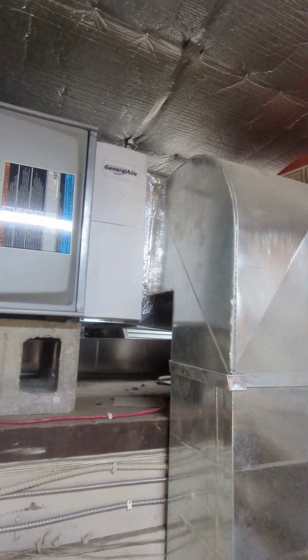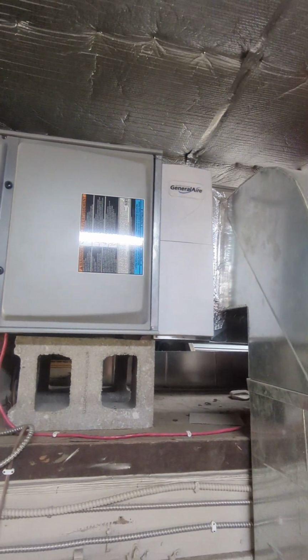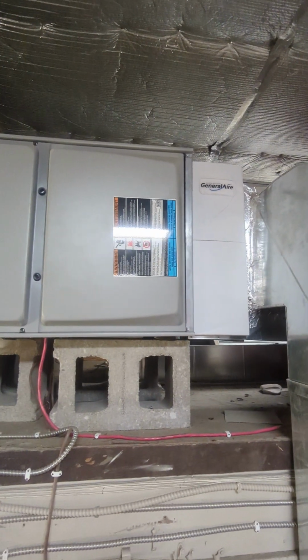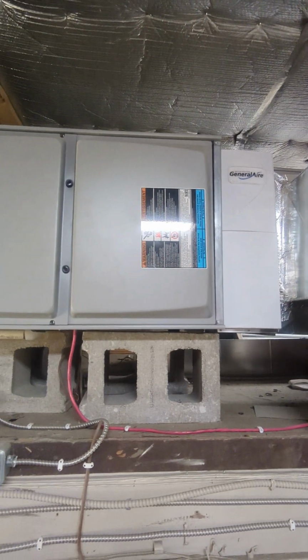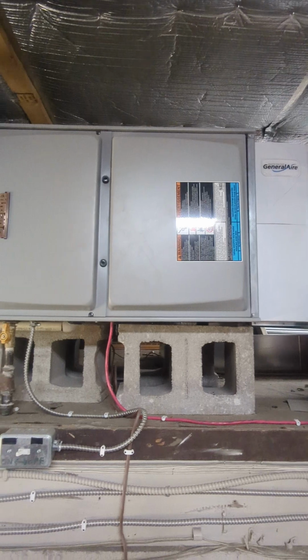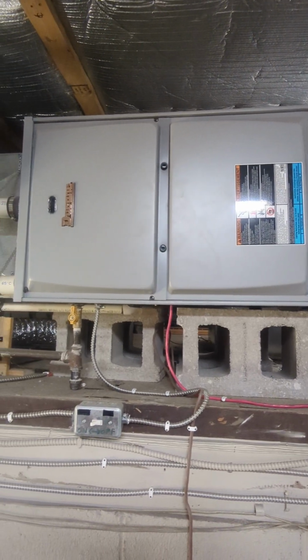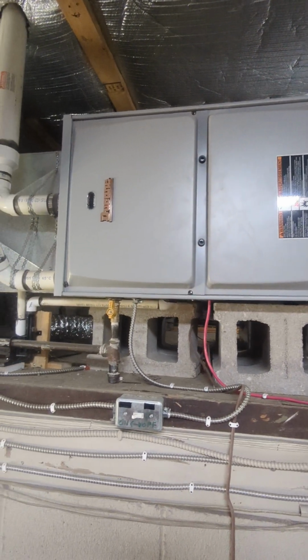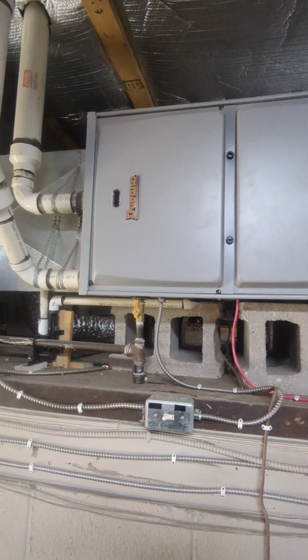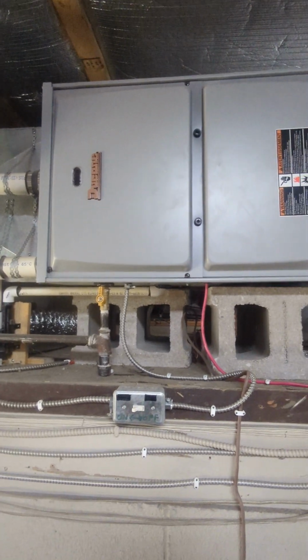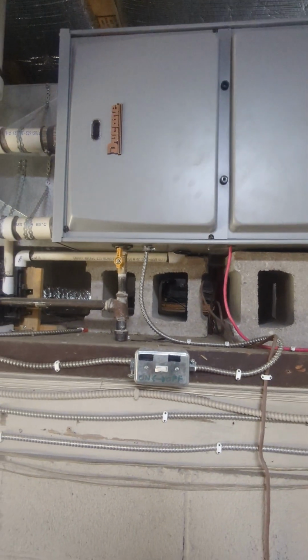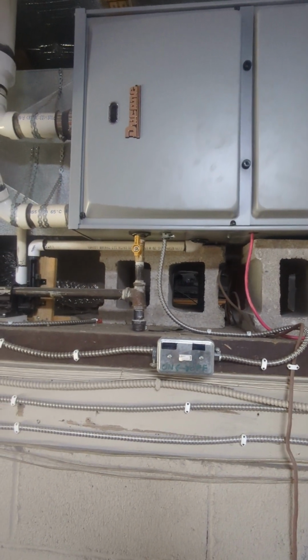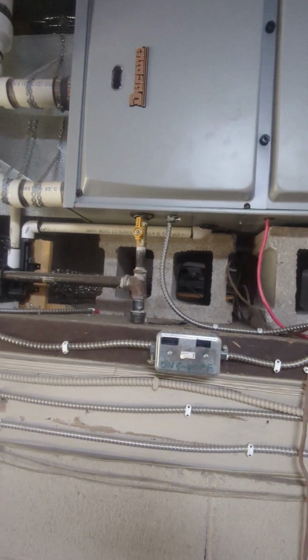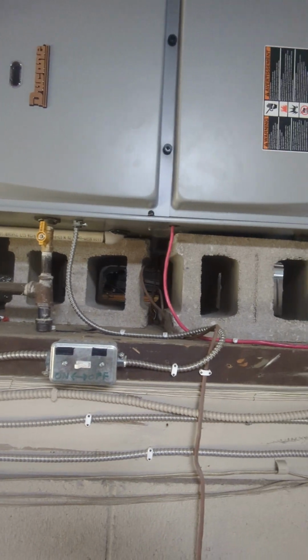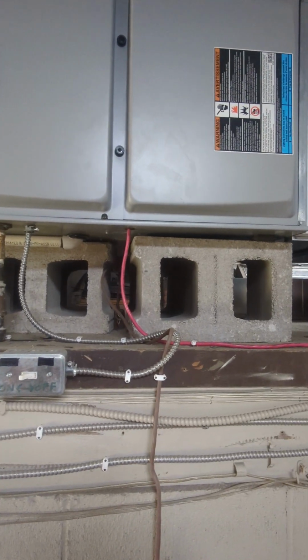It's horizontal. So the bottom of the furnace comes out. That's where the air filter rack goes on. We have it up on bricks. We also have it hanging with aircraft cable. You can't see that because it's so thin. So when you do it like this, you have to have it high enough off the ground to allow you to get things in from the bottom. We've brought the gas in through the bottom. We've brought the power in through the bottom. And we've brought the stat wires in through the bottom.